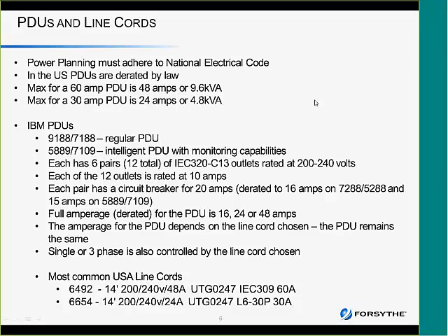And the line cords that I typically see in the US are the 6654, which is known as an L6-30P, which is a 30 amp line cord, so it would be derated to 24, or a 6492, which is a 60 amp IEC 309 derated to 48. And more, we're trying to get people to go with the 60 amp line cords, because otherwise, and you'll see when I show you some of the Power 8 numbers, what we're seeing is that people are having to have a lot more PDUs, and it gets very, very frustrating.